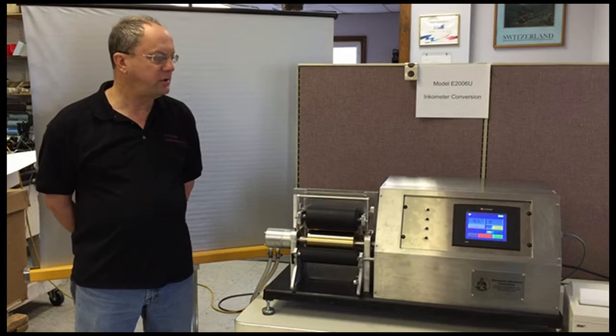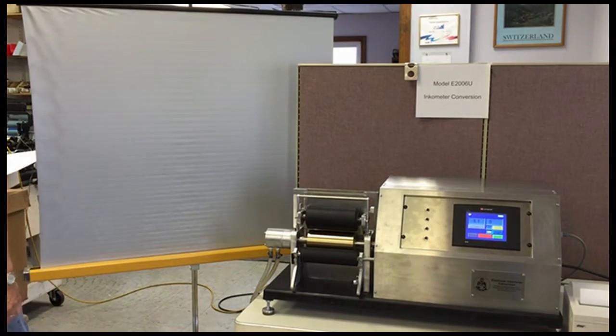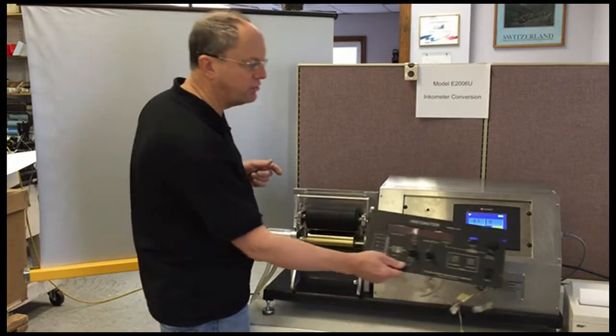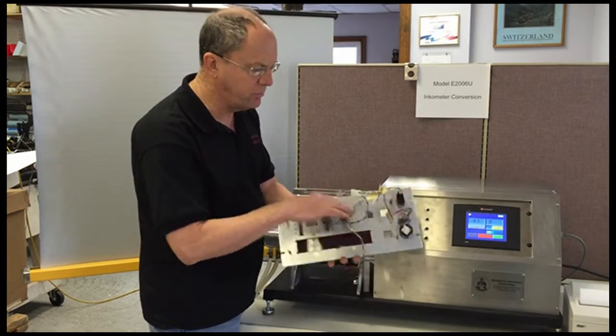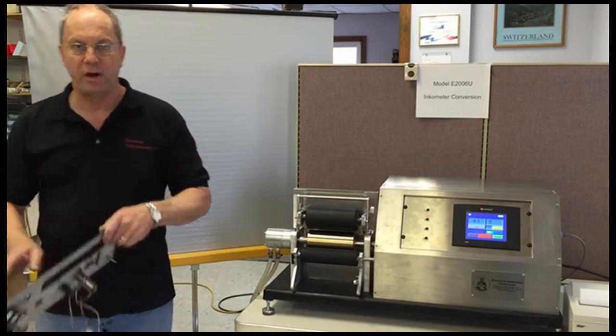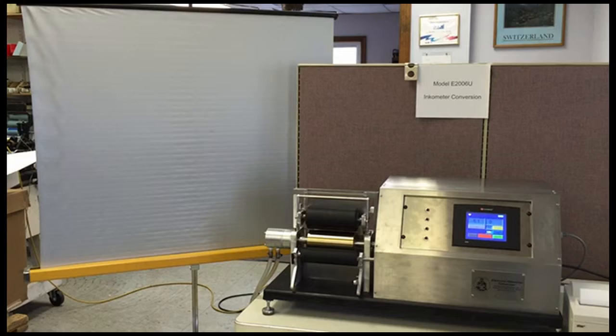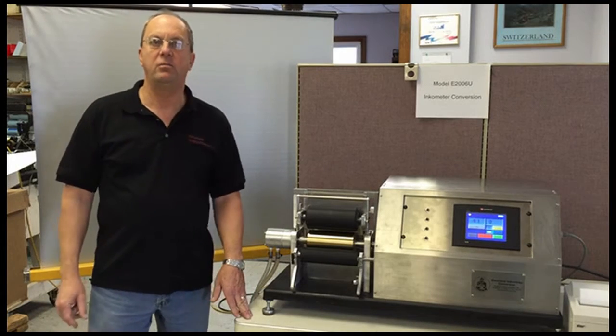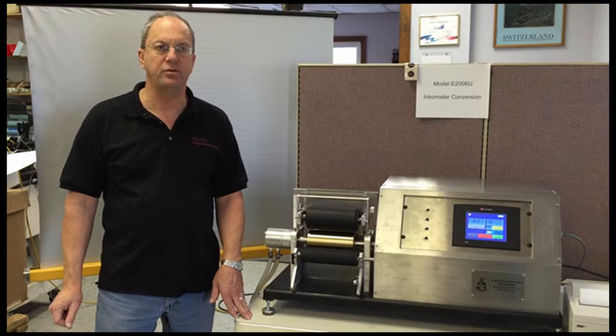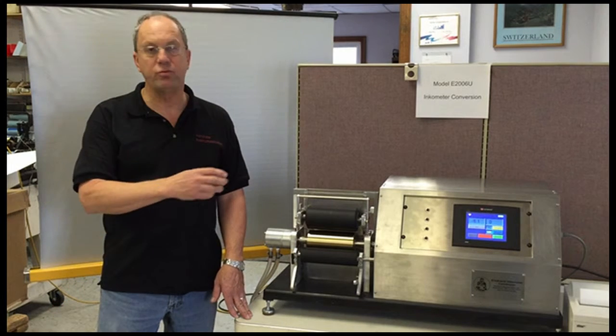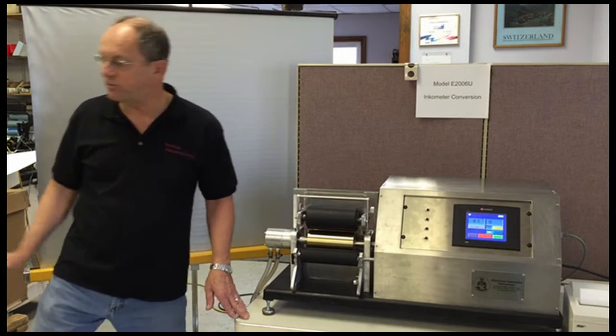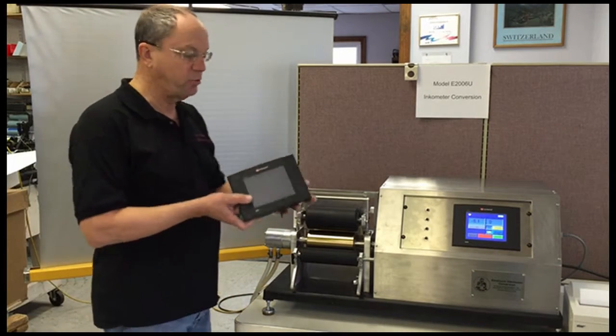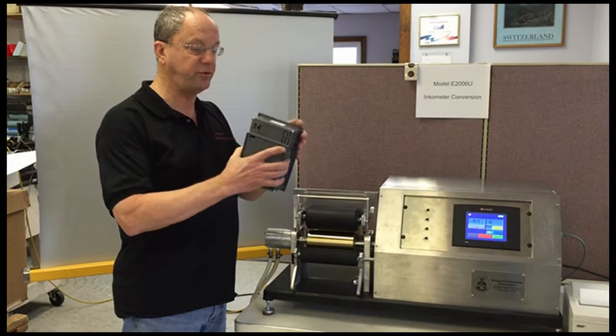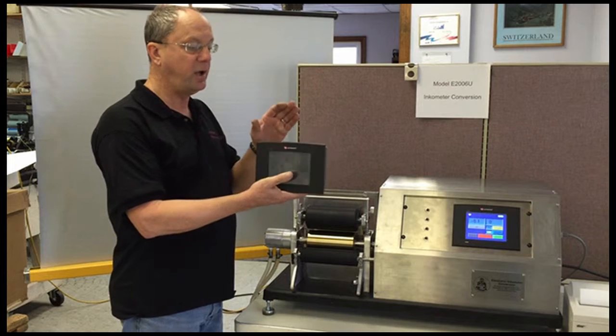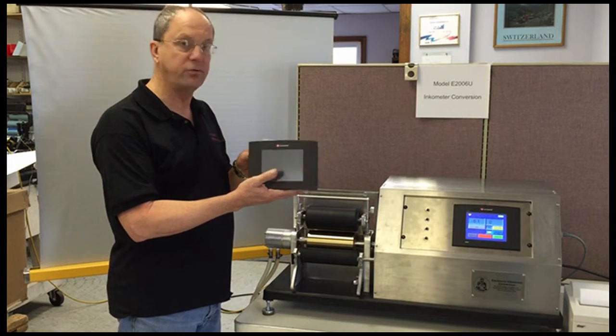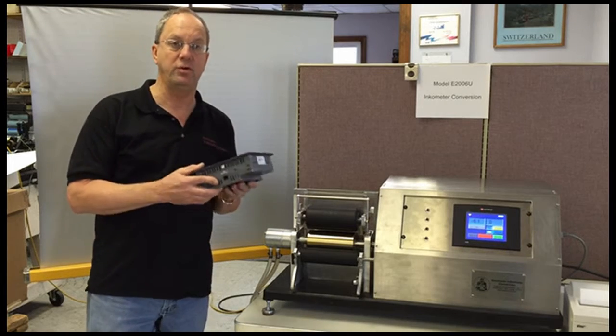Now, if you recall, on these model 106s, the original machine utilized a control panel such as this, with some controls on it. And then within the machine, there were a number of printed circuit boards, power supplies, connectors, and so forth that were often problematic in the field in terms of operation. So what we've done is we've eliminated all of those electronic components, and we have replaced them with one simple device, being this flat screen PLC. All of the connections and the signal conditioning and all the control features go through this device, and we're going to talk a little bit more in detail about this.